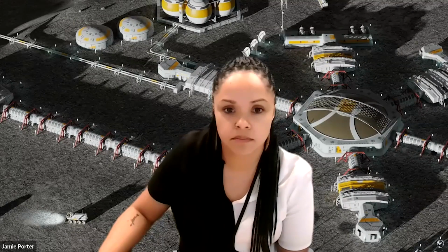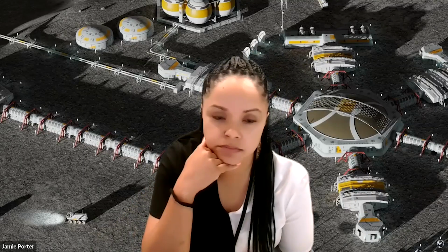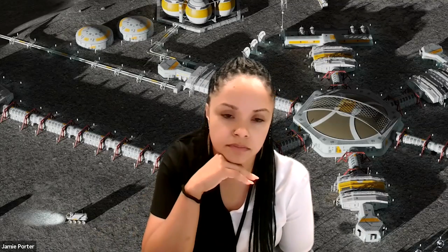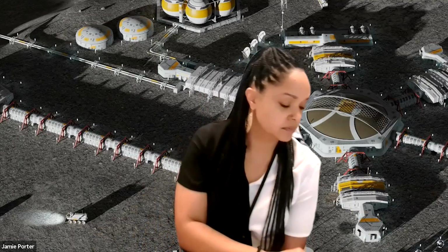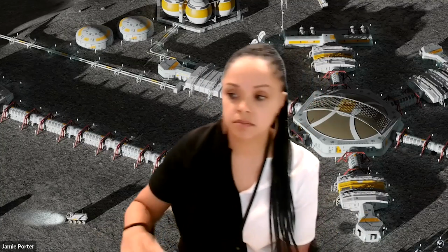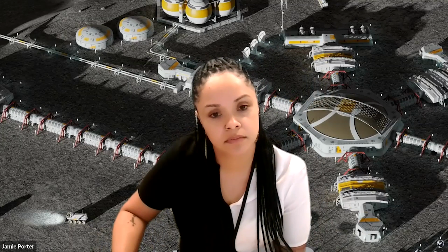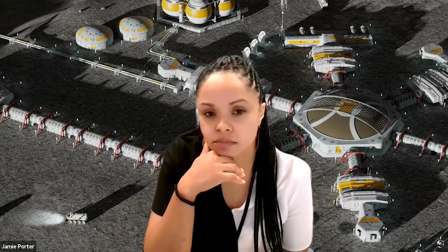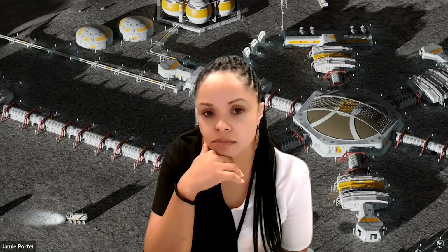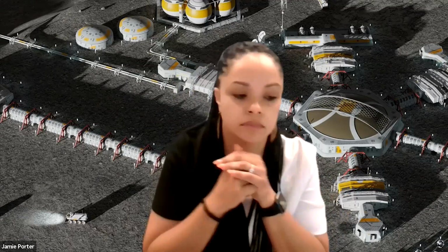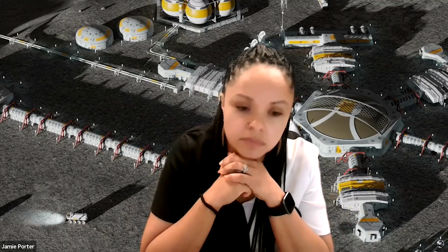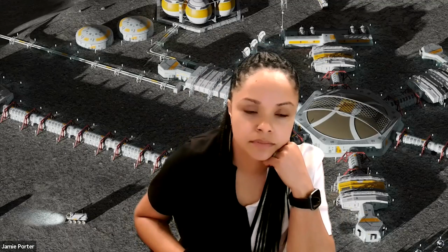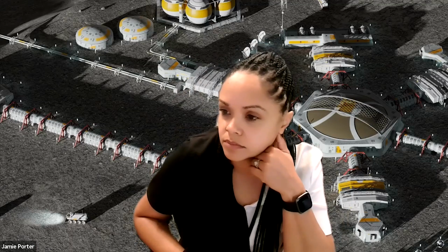One thing I could add there, Ron—this is Tim—we have always had issues with payloads and other utility type loads surpassing their inrush and surge requirements, which then would trip the electronic circuit breakers, the RPCs. Out of all the lessons learned in passing down requirements to the payloads, it's usually that inrush and surge these loads experience on turn-on that would trip our breakers. That gave us a lot of problems in testing—they would do waivers against it, fly them, and then we'd end up having trips on orbit. So it's imperative that we build our EPS system utility grade, able to handle these typical inrush and surge requirements.